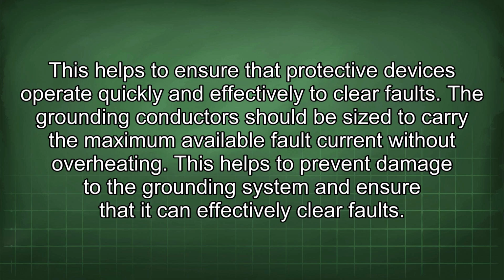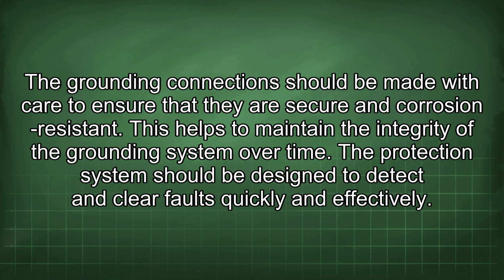The grounding conductors should be sized to carry the maximum available fault current without overheating. This helps to prevent damage to the grounding system and ensure that it can effectively clear faults. The grounding connections should be made with care to ensure that they are secure and corrosion resistant. This helps to maintain the integrity of the grounding system over time.